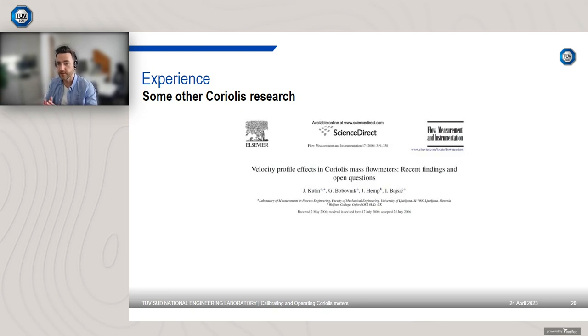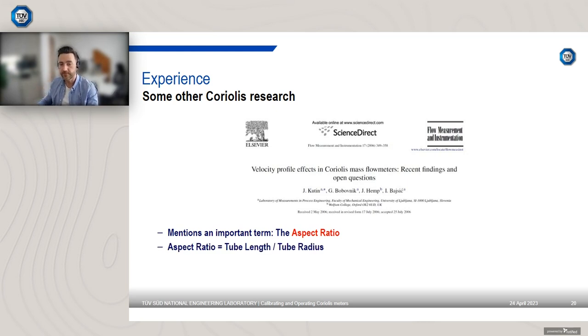So there has been some other research by other NMIs, so National Measurement Institutes, designated institutes, universities, and also meter manufacturers. So some of the findings, this is a paper here back in 2006, so just around about the time I started at NEL a couple of years before, and they discovered the velocity profile effects in Coriolis mass flow meters from some small scale research. They mention an important term, which is the aspect ratio of the device. So you might have heard that mentioned. The aspect ratio is the tube length divided by the tube radius.